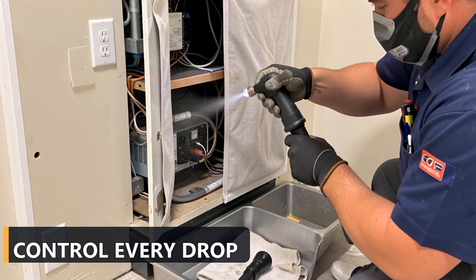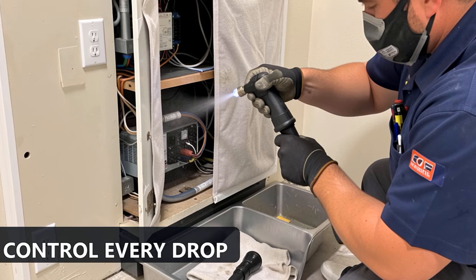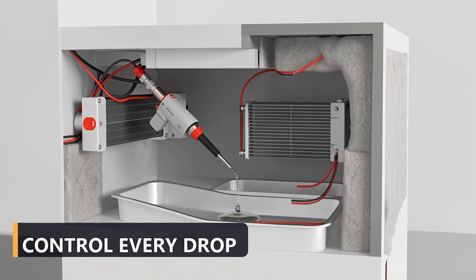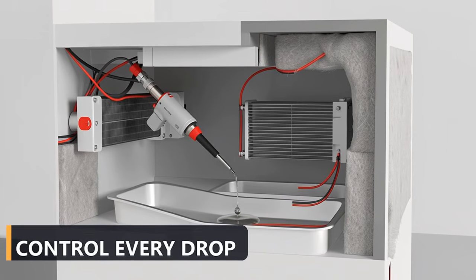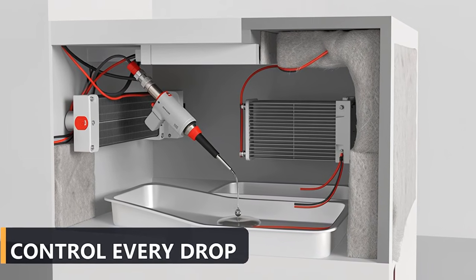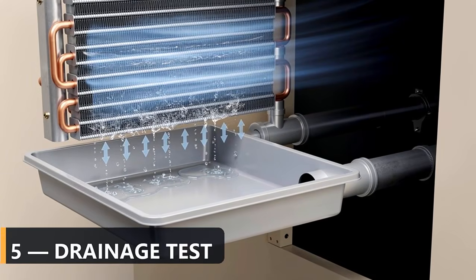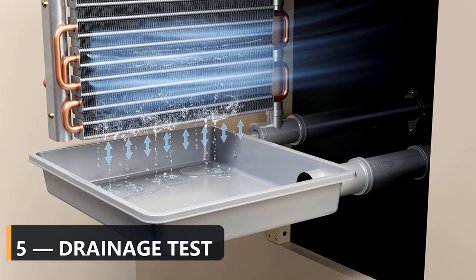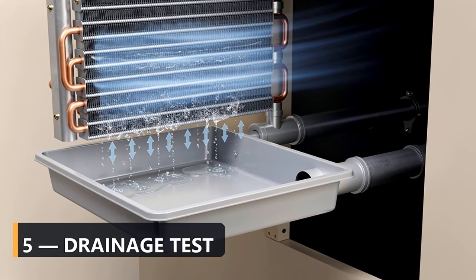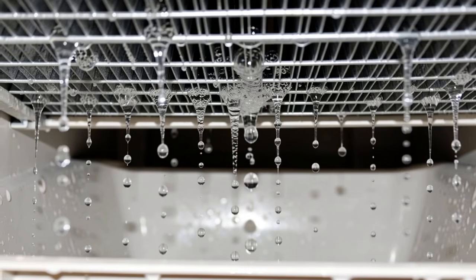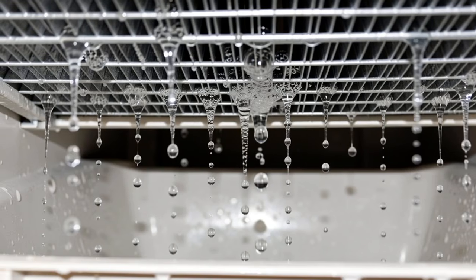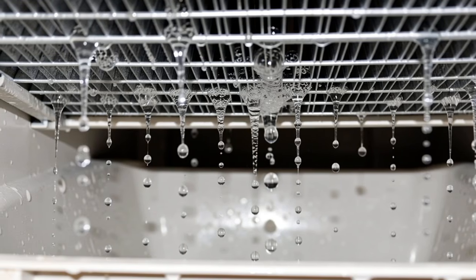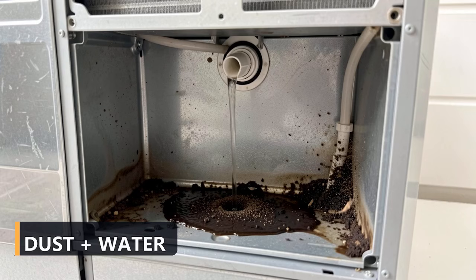That is why the dramatic thumbnail version of this experiment is dangerous when copied literally. Pouring an open bottle across the face of an installed coil gives you almost no control over volume, direction, or runoff. A technician protects adjacent components, uses controlled application, collects wastewater, and confirms the cabinet is dry before reassembly. The secret is not a stronger chemical. It is controlling where every drop goes.